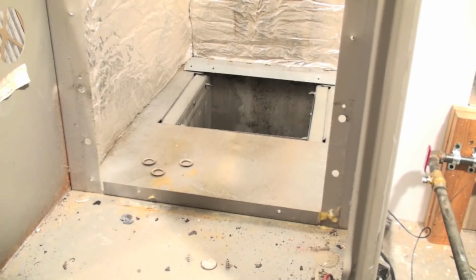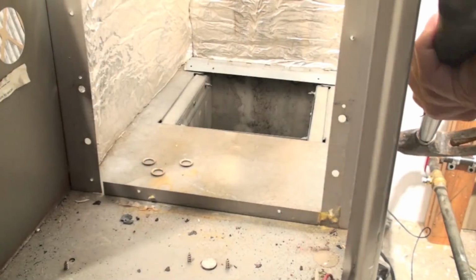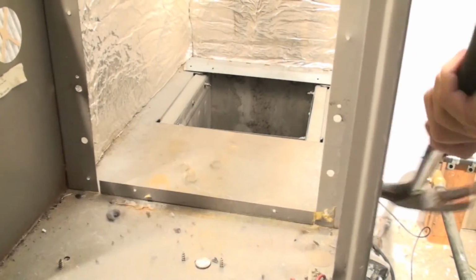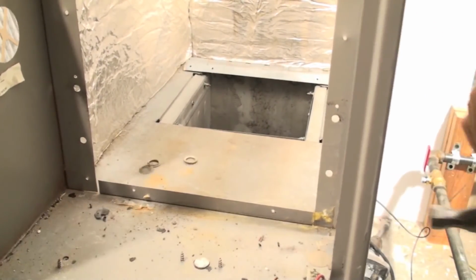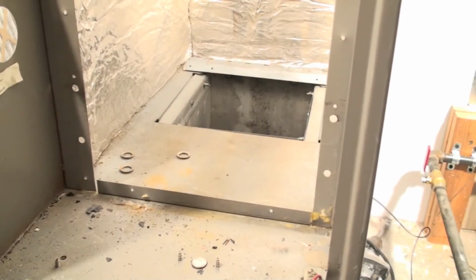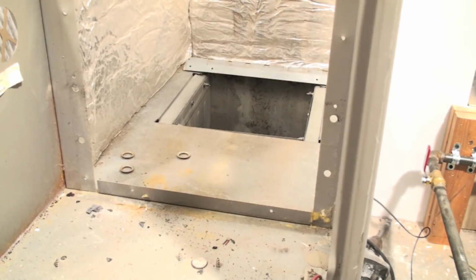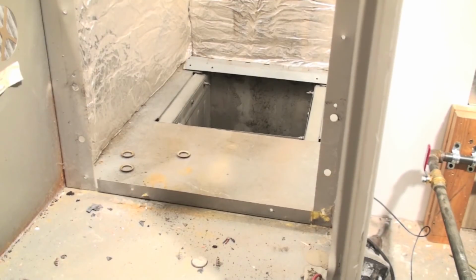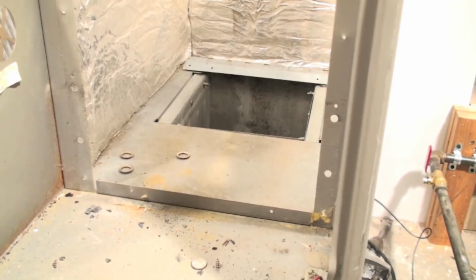And if you take a hammer, and I'm going to hit the side of this with a hammer, you can hear those rings bounce in there when you hit it. You'll probably just see it in the burners anyway, but it was a little thing I used to do sometimes just to make sure. And that's a GMP heat exchanger. If you come onto one, look at it very close because it probably has failed, but you just got to watch those burners.